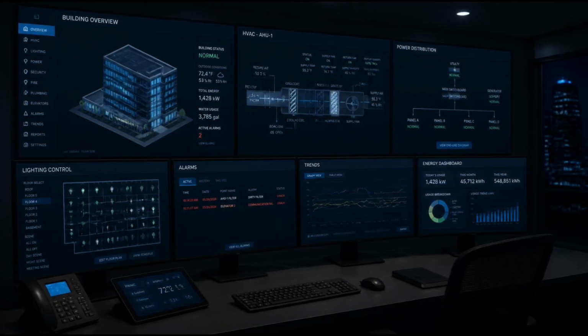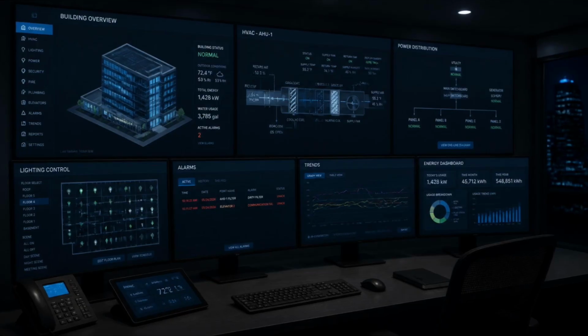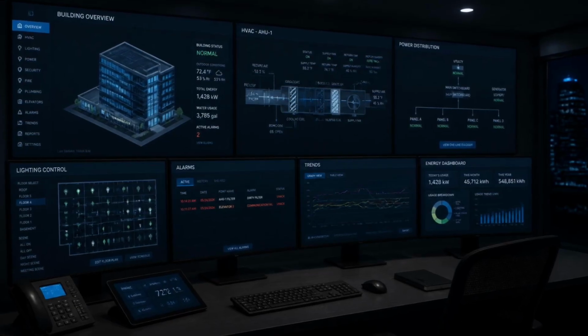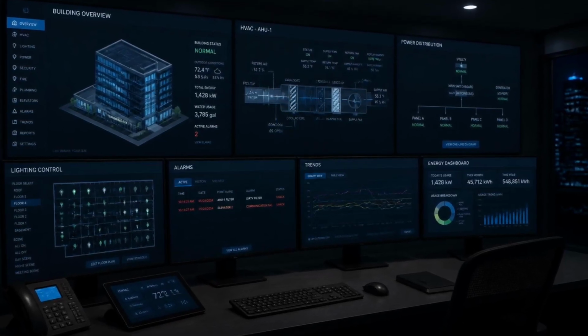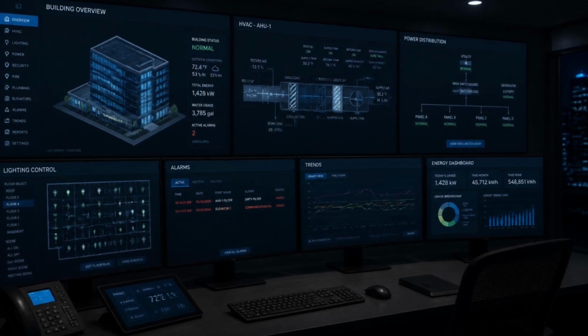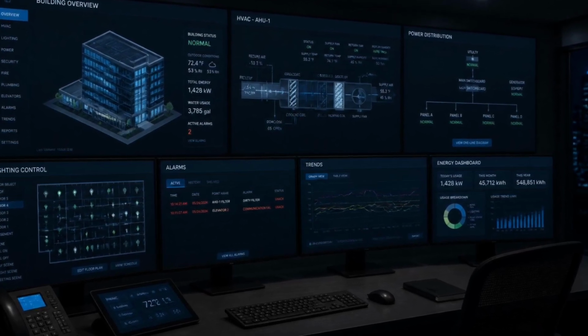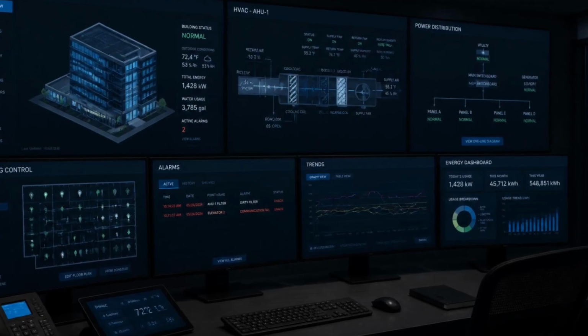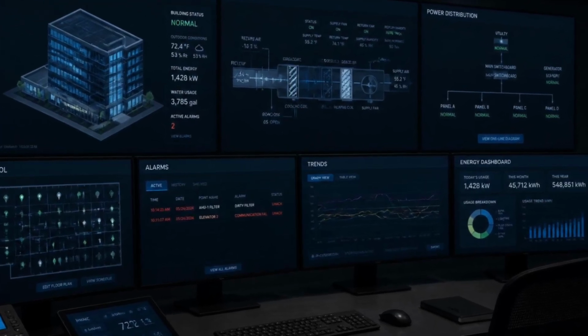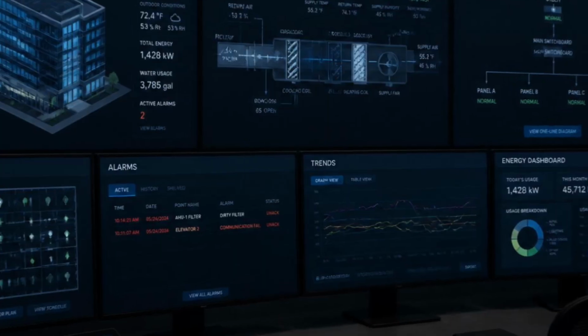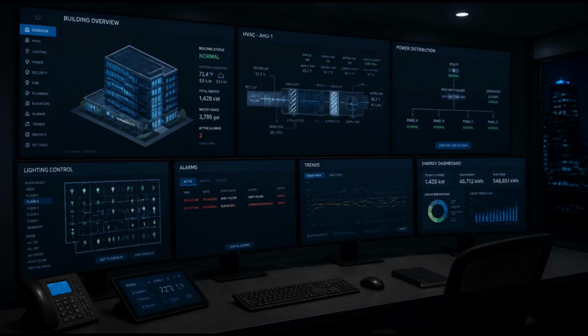Balanced airflow helps reduce hot and cold spots. Even within a single zone, the goal is to deliver air in a way that creates even, consistent conditions throughout the space, not too warm in one corner and too cool in another, not stuffy near the center and drafty near the diffuser. The placement of diffusers, the volume of air delivered, and the configuration of the return system all work together to encourage thorough, even air distribution within each zone.